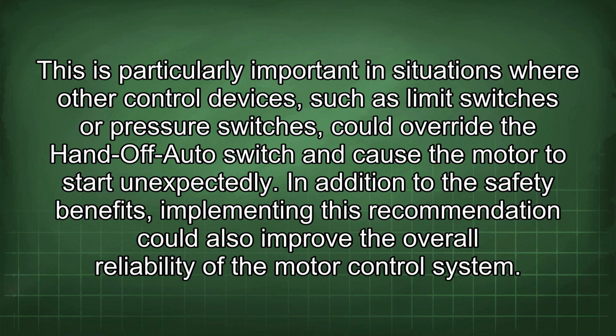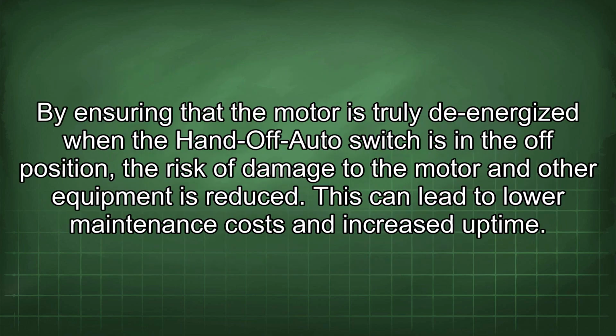In addition to the safety benefits, implementing this recommendation could also improve the overall reliability of the motor control system. By ensuring that the motor is truly de-energized when the hand-off-auto switch is in the off position, the risk of damage to the motor and other equipment is reduced. This can lead to lower maintenance costs and increased uptime.